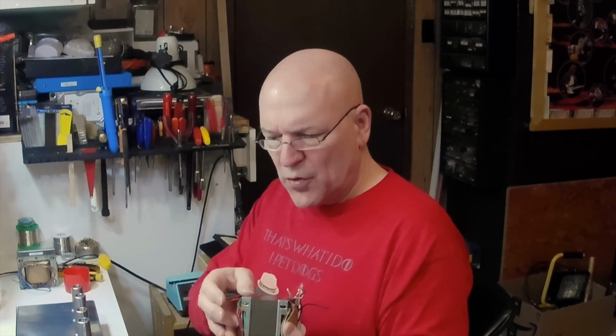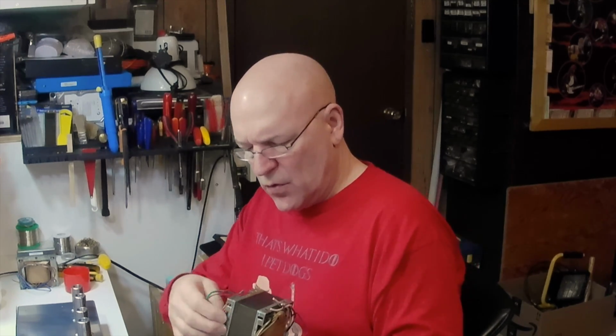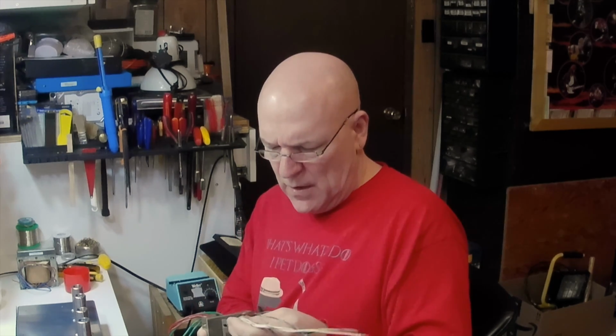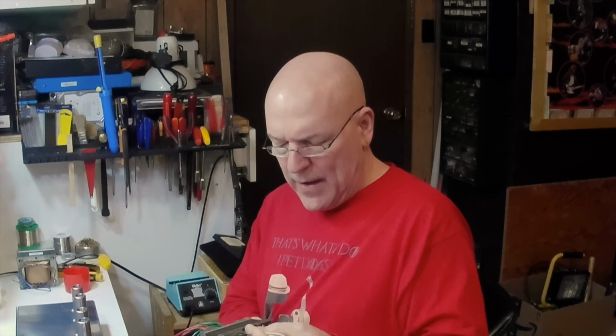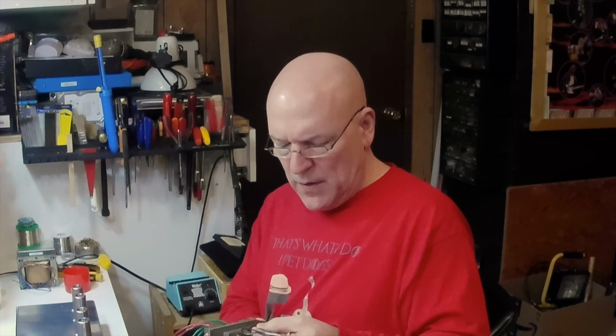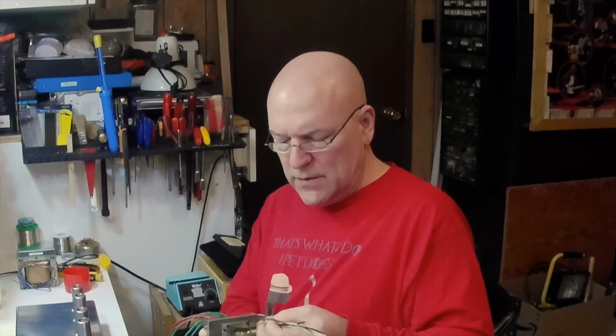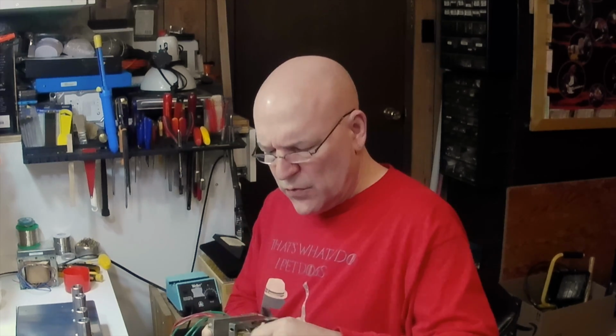You have your primary and secondary sides of your transformers. On this transformer, you have a black with a red stripe, and a black with a white stripe. You also have a white, and then a white with a red stripe, and a white with a black stripe. Those all correspond to the different ways you might wire the mains for wherever you are. Of course, we're in North America, so I'll be wiring this for 120 volts.